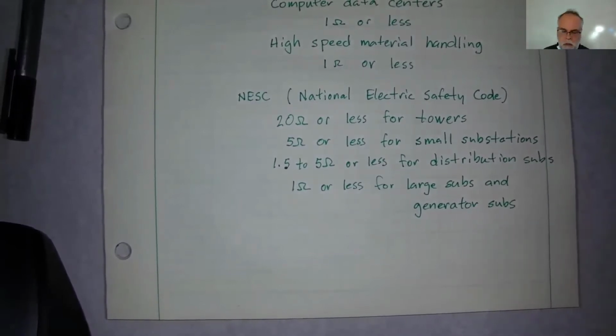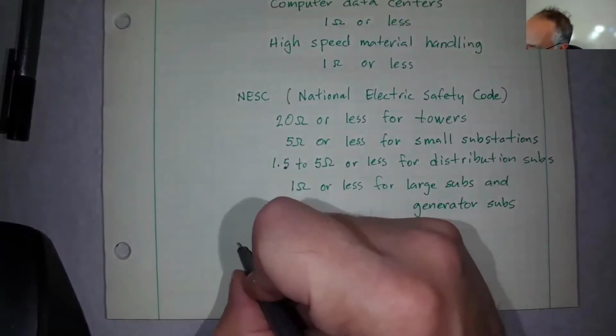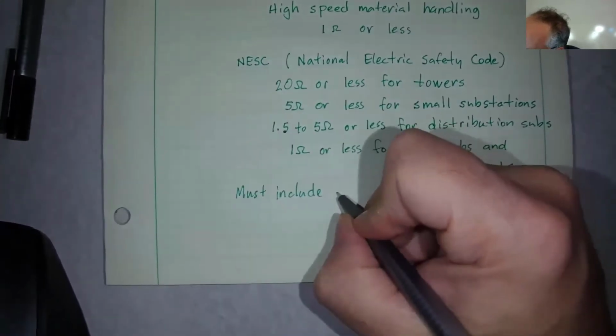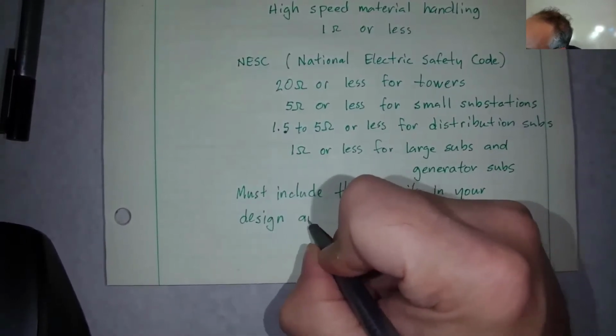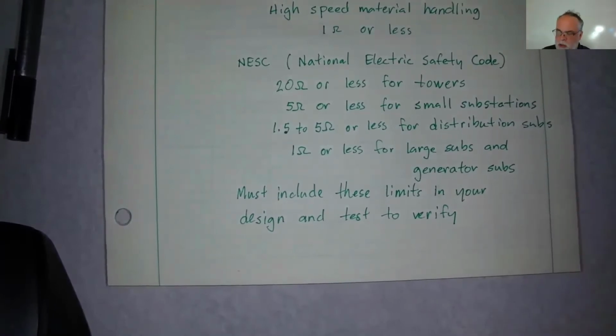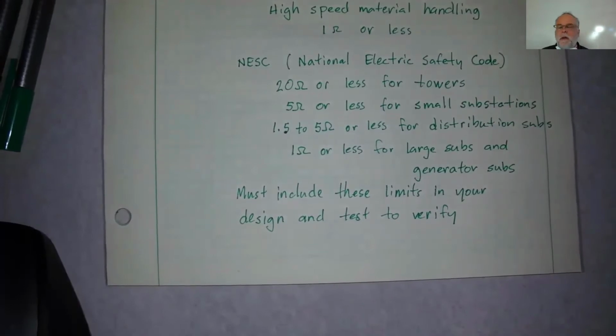So does that make sense? So when they're designing a substation or designing a transmission line, they're going to have to come up with the appropriate grounding for the towers, for every one of the towers. And then you've got to test that to make sure it's the required resistance or less. Does that make sense?